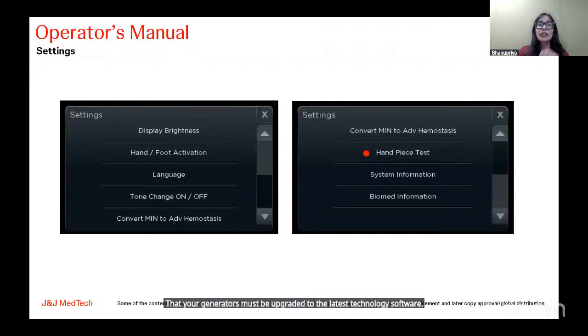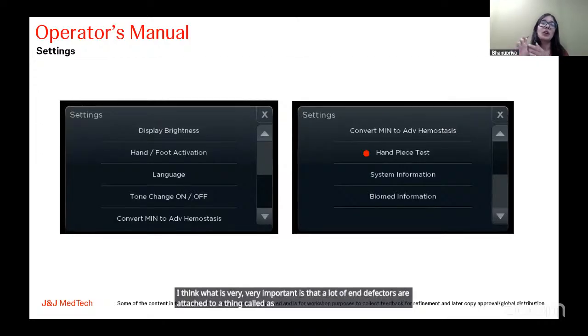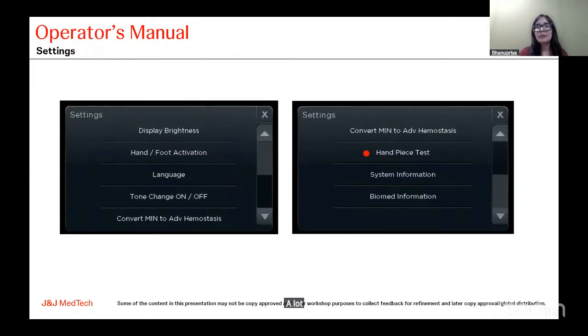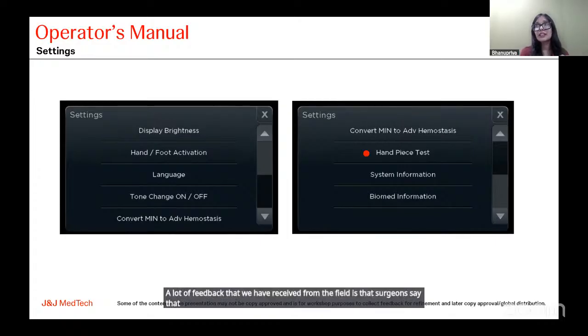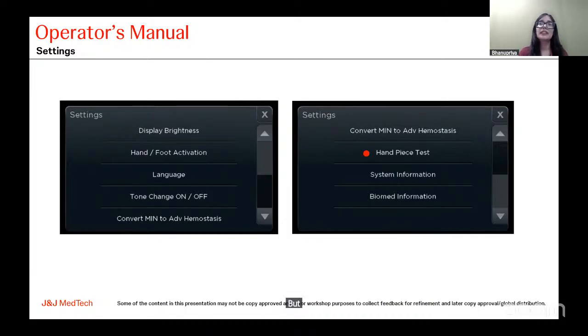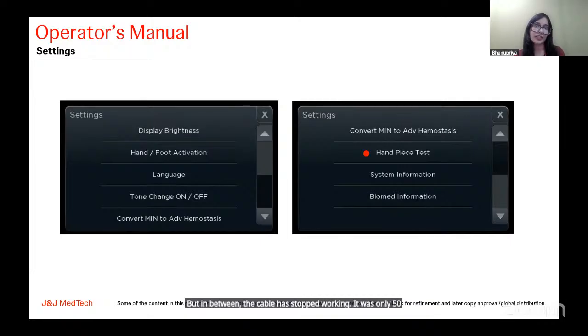I think what is very, very important is that a lot of end effectors are attached to a thing called the handpiece, or a gray color cable that you might be having. A lot of feedback that we have received from the field is that surgeons say that the cable is to be reused for 95 or 100 uses, but in between the cable has stopped working. It was only 50 uses and now the cable is not working.